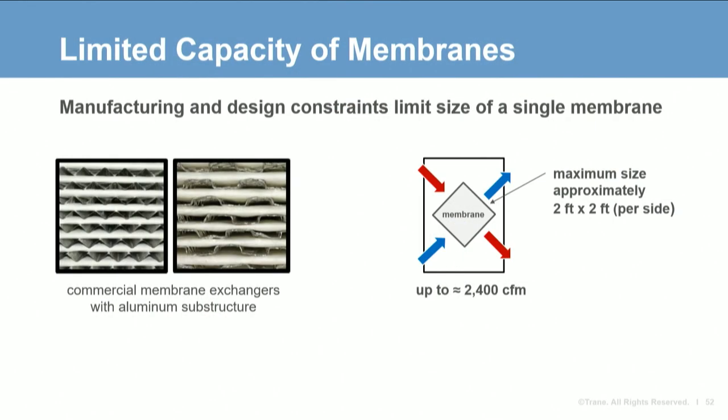Unlike aluminum plate heat exchangers, membrane heat exchangers are made from a pliable membrane material. Most commercial exchangers have aluminum mesh or flutes to provide structural support to withstand static pressure differentials between the supply and exhaust airstreams. Membranes are more limited in size compared to sensible metal plate exchangers — the largest exchangers are approximately 2 feet by 2 feet. Using a 2-by-1 aspect ratio, that's only 2,400 CFM.